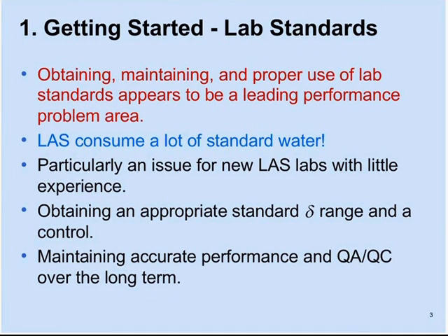The other fact is that the lasers consume a lot of lab standard water. Lots of auto runs, long auto runs, little vials you need to fill up. And so there's a more pressing issue with how you come up with laboratory standards and maintain them over time and maintain the isotopic fidelity so that you get the best possible results. As I mentioned, this is a particular issue for new laser labs that have staff that may have little experience, that don't realize evaporation is a problem, and those sorts of things.